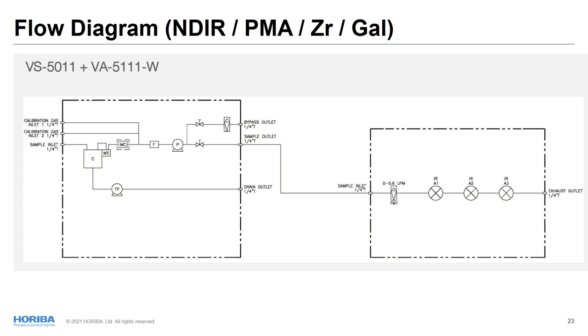Basically, the sample panel is designed to push the sample gas to fill into the analyzer. If the VA-5000 works with an existing sample unit, then we just need to tune the sample pressure and the flow to feed into the gas analyzer, because the sample gas condition needs to be within the specification, which is 0.72 psi pressure. Most of the other analyzers may accept a wider range, but for this one we simply need to lower the sample flow. And just for your information, HORIBA also has our own design wall mount sample system available, so we are flexible however you like for your project.